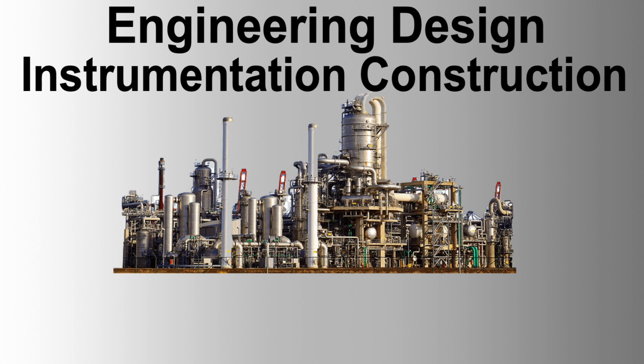Quality assurance. Loop tests shall be performed by qualified personnel with experience in instrumentation and control systems. Testing equipment shall be calibrated and maintained to ensure accurate and reliable results. Regular audits shall be conducted to ensure that loop testing is performed consistently and in accordance with the project specifications and standards.